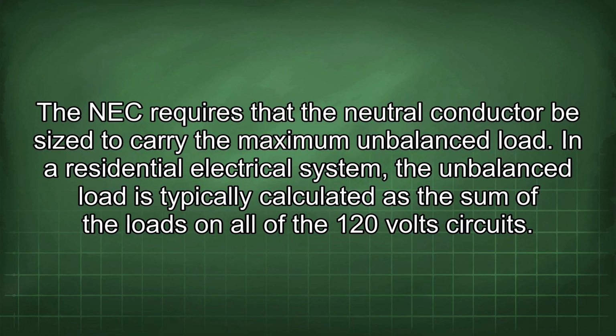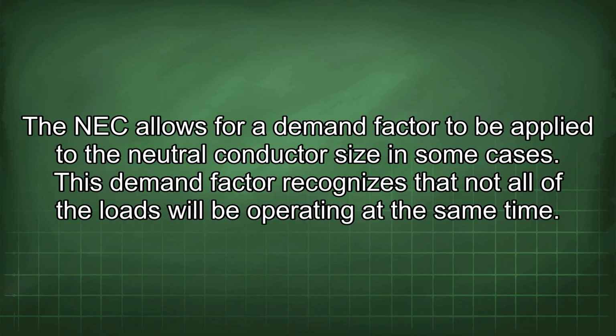The NEC requires that the neutral conductor be sized to carry the maximum unbalanced load. In a residential electrical system, the unbalanced load is typically calculated as the sum of the loads on all of the 120 volt circuits. The NEC allows for a demand factor to be applied to the neutral conductor size in some cases. This demand factor recognizes that not all of the loads will be operating at the same time.